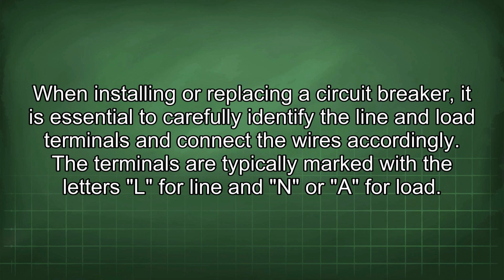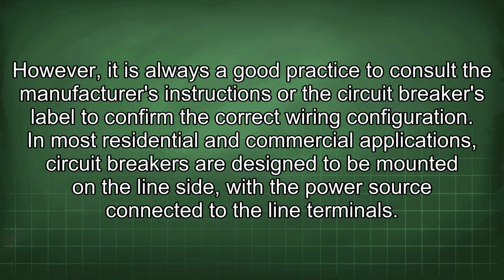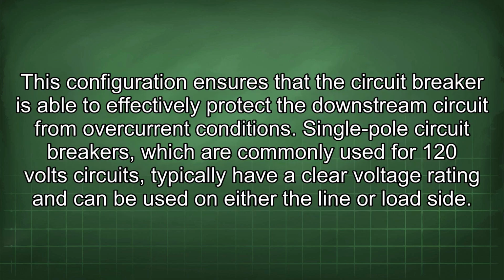When installing or replacing a circuit breaker, it is essential to carefully identify the line and load terminals and connect the wires accordingly. The terminals are typically marked with the letters L for line and N or A for load. However, it is always a good practice to consult the manufacturer's instructions or the circuit breaker's label to confirm the correct wiring configuration. In most residential and commercial applications, circuit breakers are designed to be mounted on the line side with the power source connected to the line terminals. This configuration ensures that the circuit breaker is able to effectively protect the downstream circuit from overcurrent conditions.